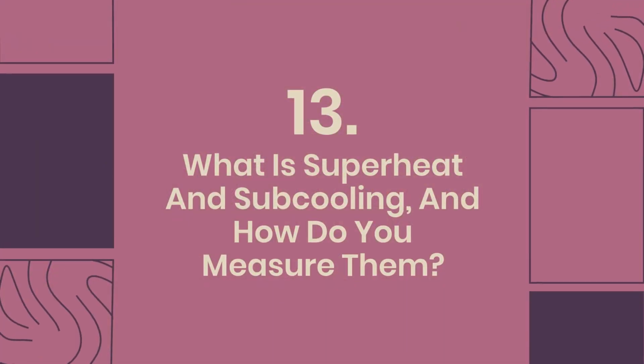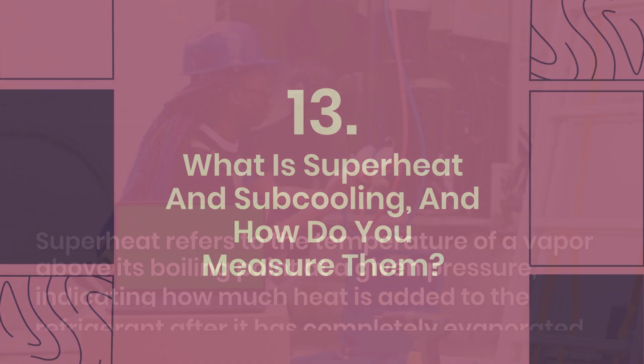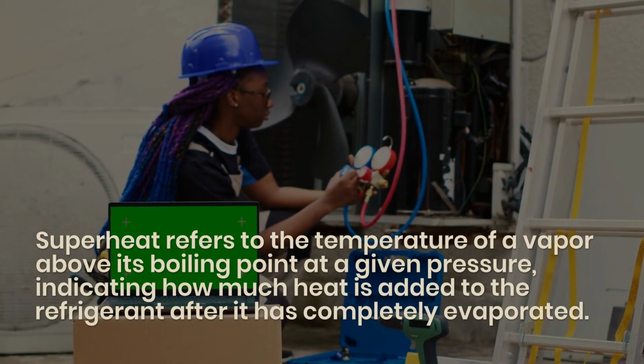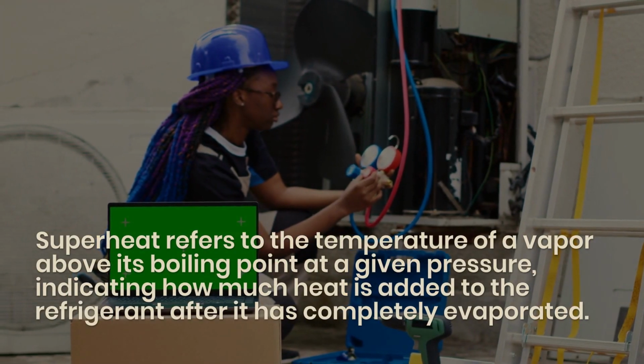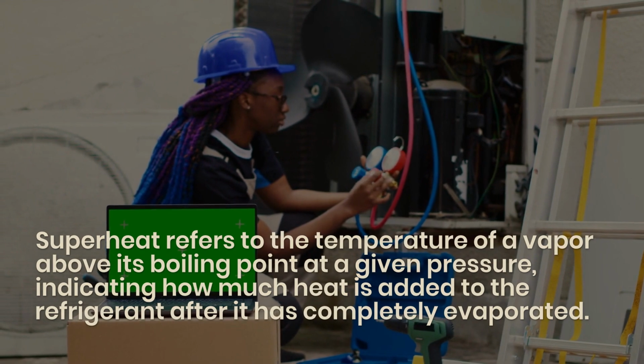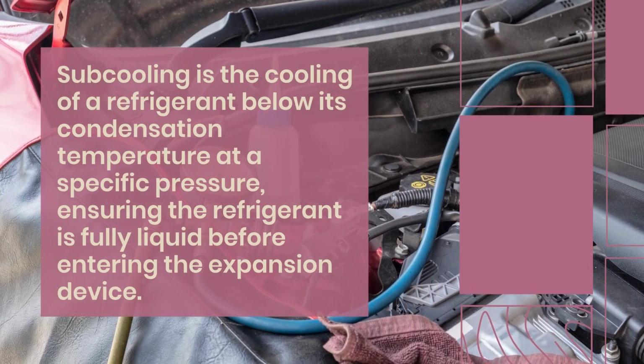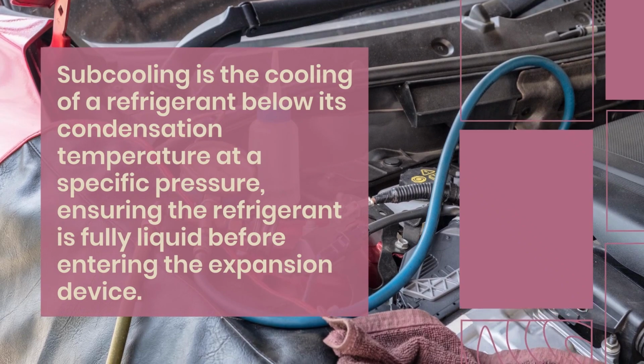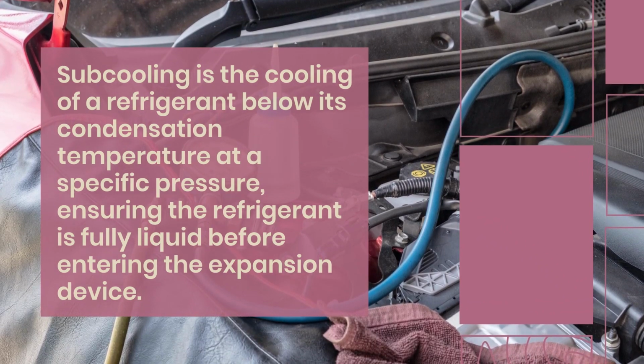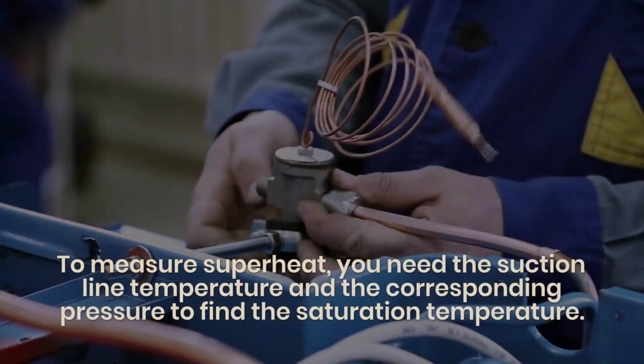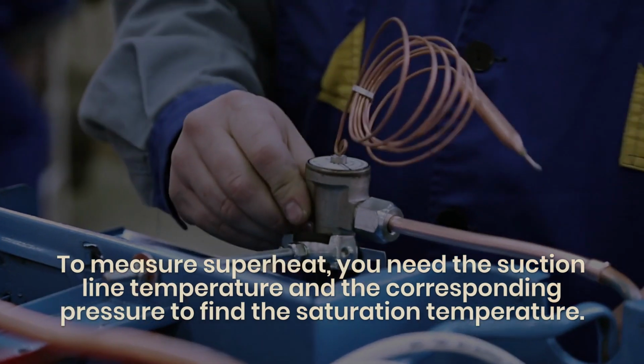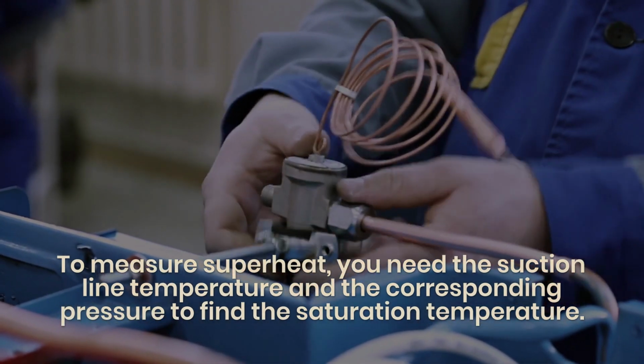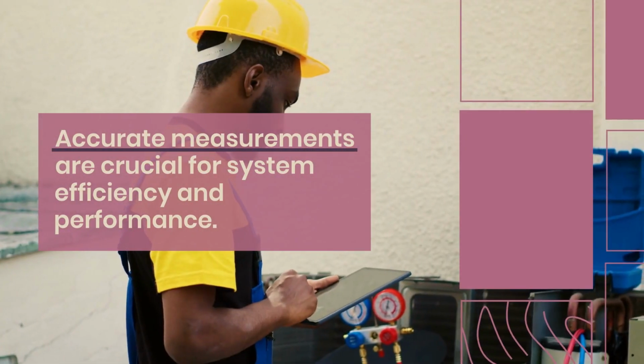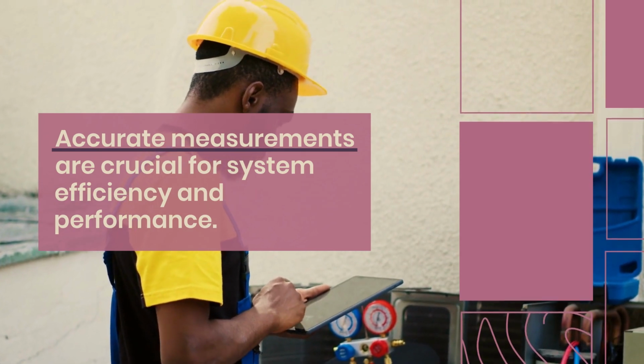13. What is superheat and subcooling, and how do you measure them? Superheat refers to the temperature of a vapor above its boiling point at a given pressure, indicating how much heat is added to the refrigerant after it has completely evaporated. Subcooling is the cooling of a refrigerant below its condensation temperature at a specific pressure, ensuring the refrigerant is fully liquid before entering the expansion device. To measure superheat, you need the suction line temperature and the corresponding pressure to find the saturation temperature. Accurate measurements are crucial for system efficiency and performance.